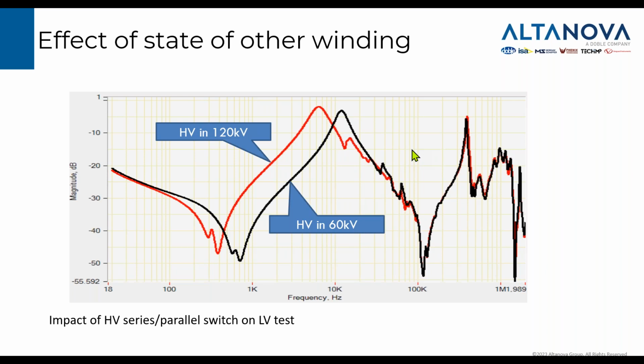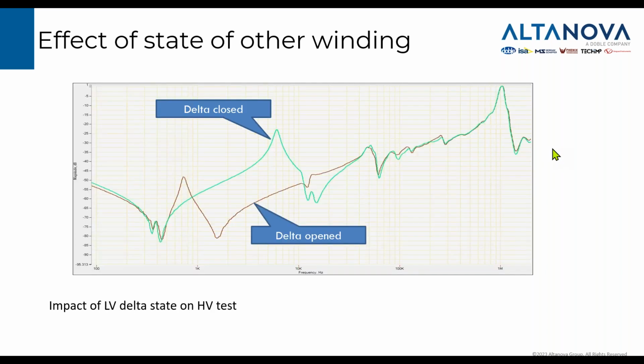So when you have such a transformer, you have to make sure you test it on this tap position or this switch position which you want it to be tested. If you have reference, you need to look at which position it was tested before. And in your report, you need to describe how you tested. It is always important to write in your report something about the test setup, so that someone who comes some years later can reinstate the same test setup.